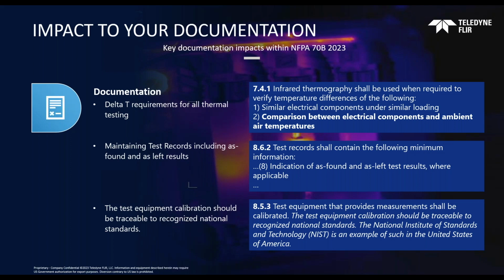It needs to be traceable to recognized national standards. One standard referenced within 70B is NIST, a common standard used for calibrated equipment. This applies to test equipment that provides measurements - clamp meters, multimeters, anything used in an electrical inspection program, as well as thermal cameras - all need to be calibrated based on the manufacturer's recommendation and documented within the system.